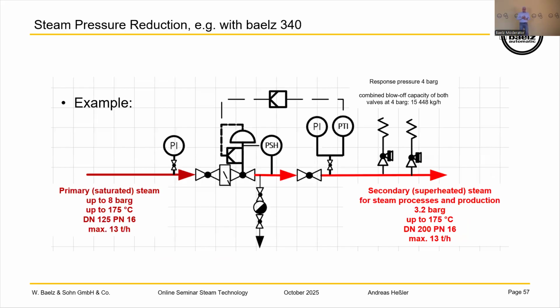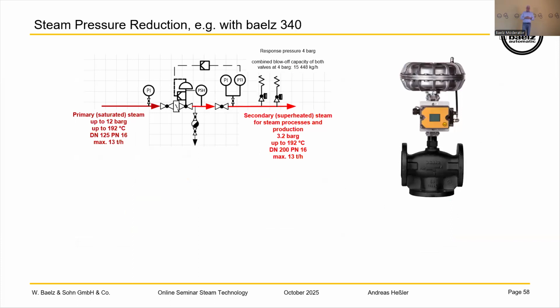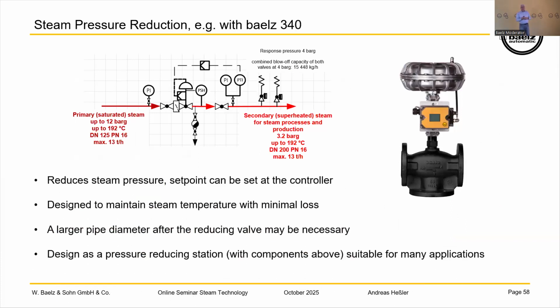The next example I want to show is a steam pressure reduction. In this case, we want to control the pressure, so we're using our 340 valve. This reduces steam pressure to a set point of the controller. Here you can see it goes from 12 bar to 3.2 bar.